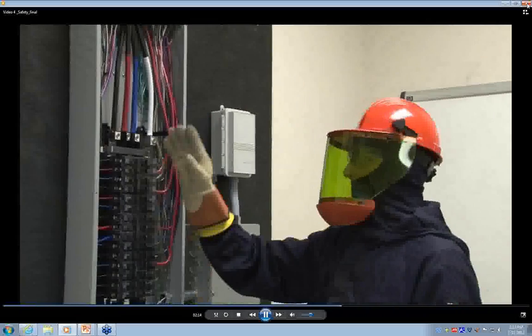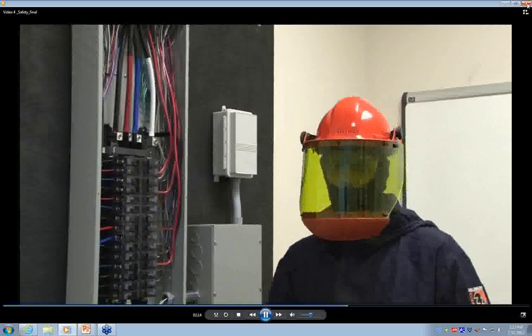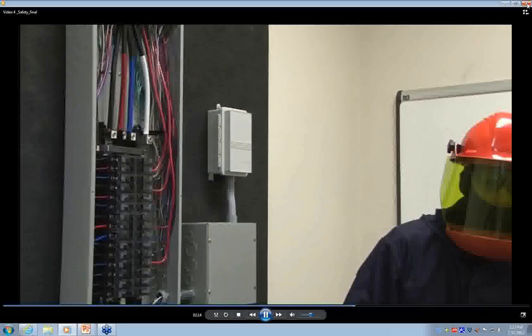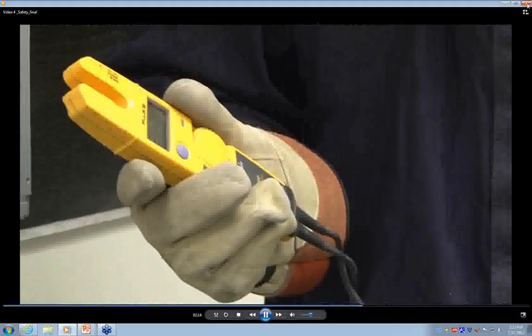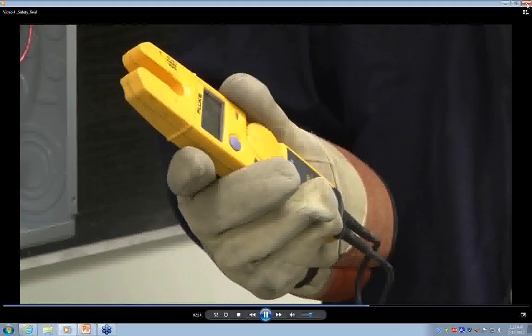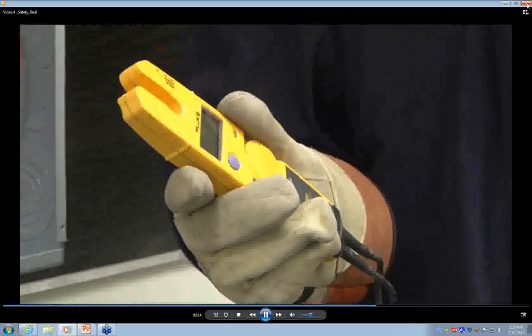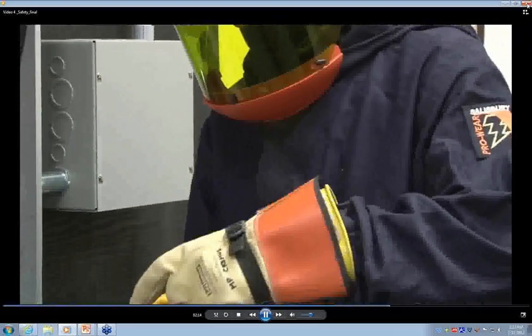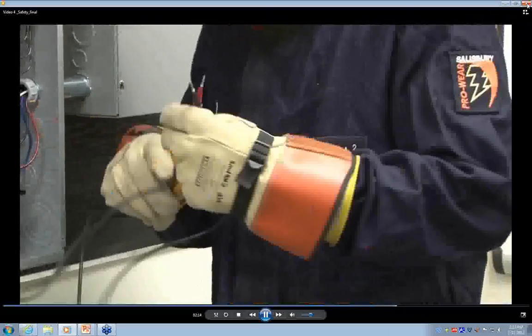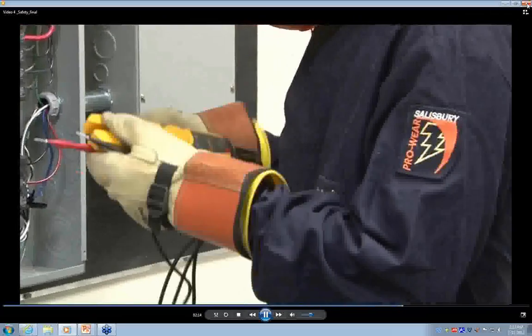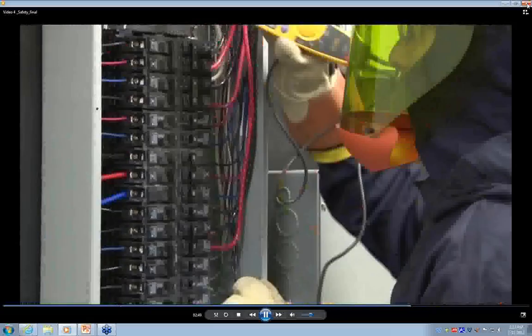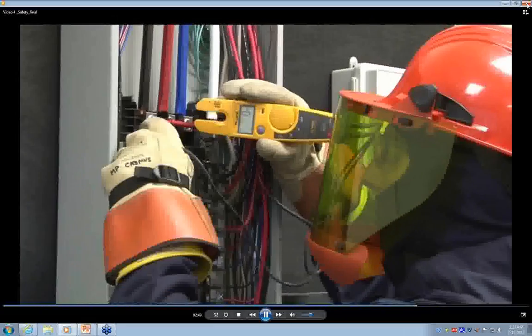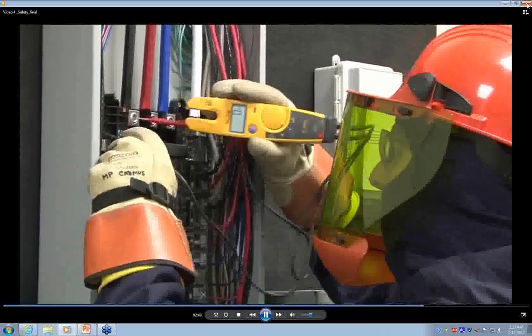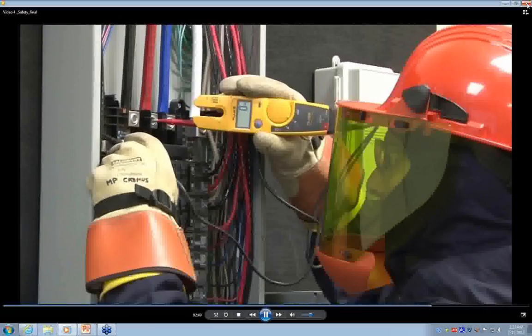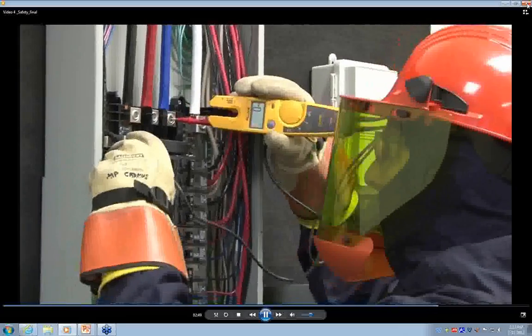We can see that the main conductors are black, red, and blue, so we know this panel is probably 208 volts. We'll confirm that with our voltage meter. We'll take our voltage readings with a Fluke T5 1000 meter. This is double insulated and good for up to 1000 volts. We'll set the meter to voltage, and we'll take multiple voltage measurements. We'll start with phase A to the neutral conductor. We should read approximately 120 volts. We'll then move on to phase B and phase C and get the same reading.